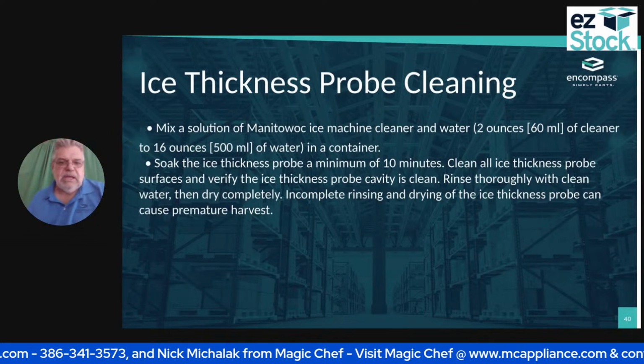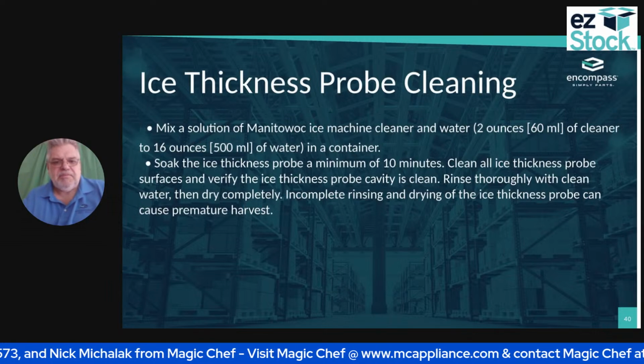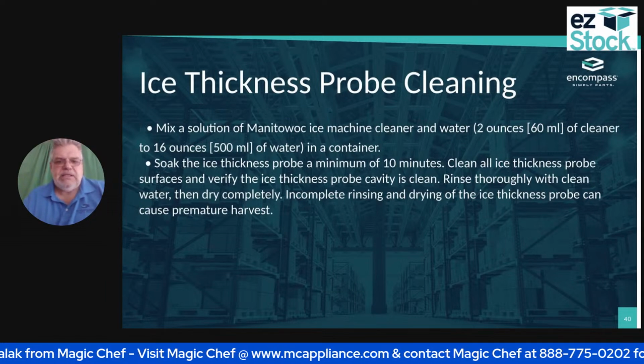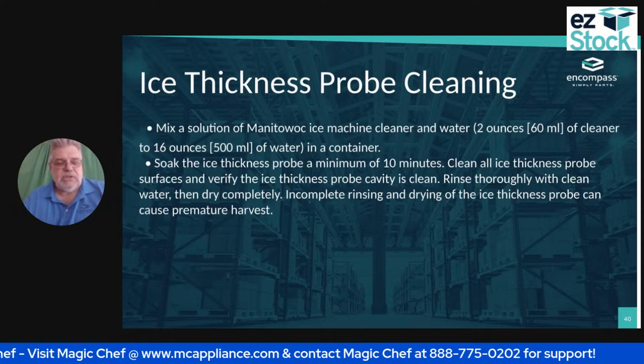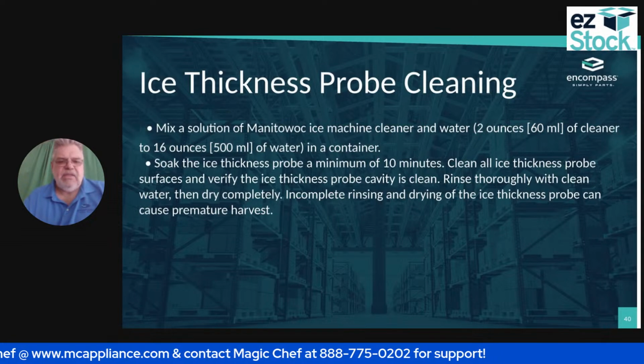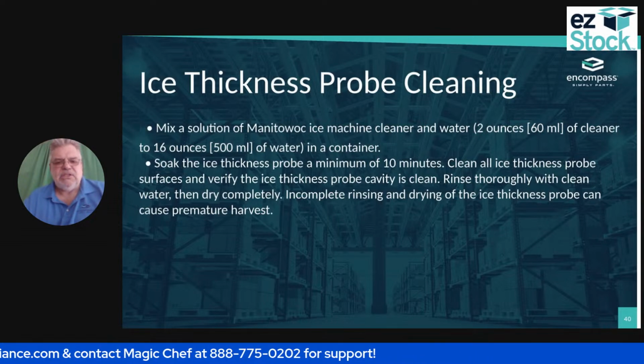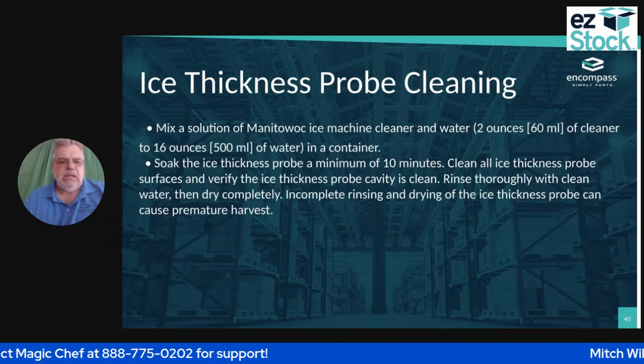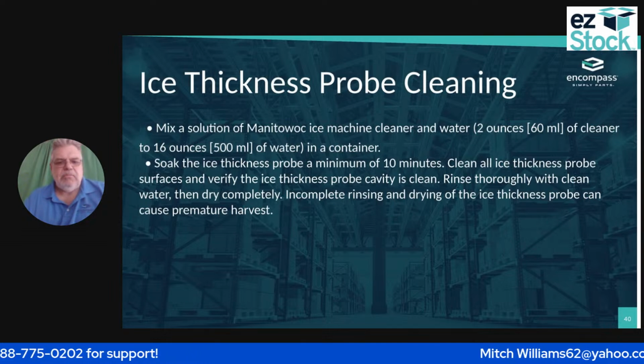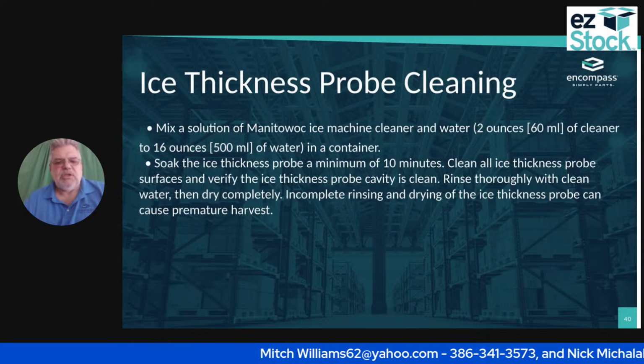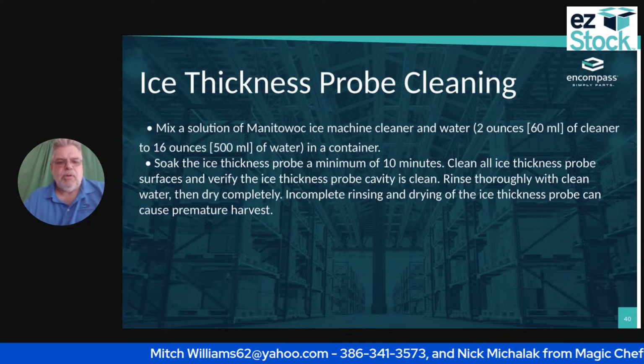Then I'm going to soak the ice thickness probe for a minimum of 10 minutes. I'm going to clean the ice thickness probe surfaces and verify the ice thickness probe cavity is clean. Then rinse thoroughly with water and dry completely. Incomplete rinsing and drying of the ice thickness probe can cause premature harvest.